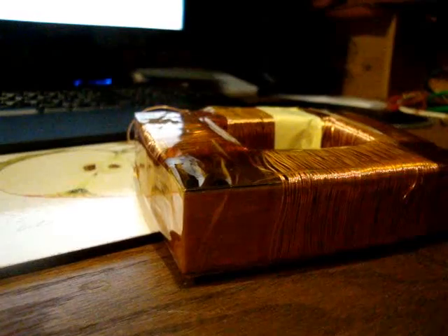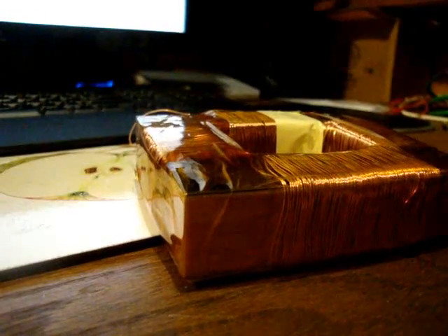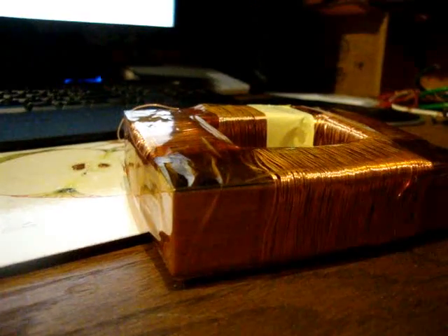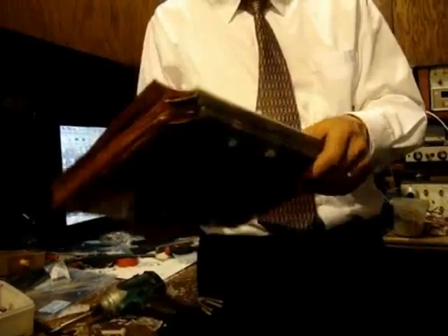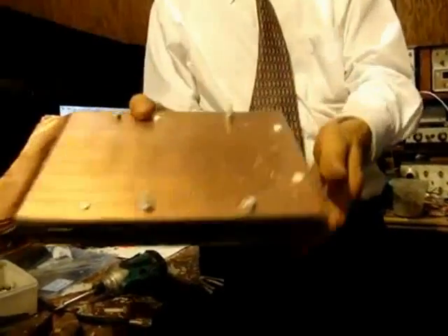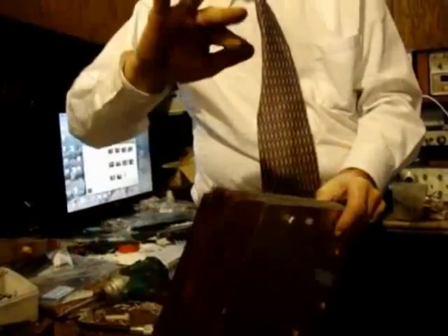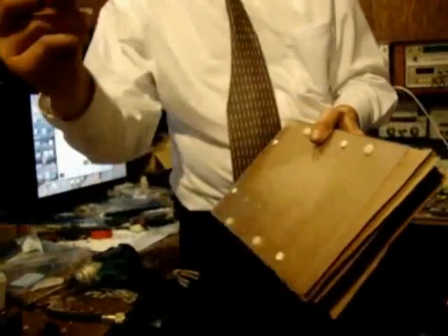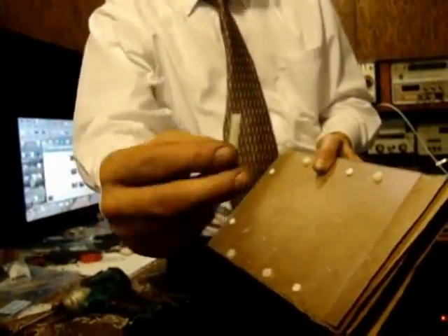Yeah, it's interesting. There's a lot of surface area around this core because each side of the core is about 5 inches in length. So I have 4 sides of 5-inch length, and the number of turns per side: one side has basically 50 turns of secondary, the other side has 70 turns of secondary, 50 and 70. So that's the 4 sides. And between primary and secondary, the flat foil is underneath at the bottom, and then the other gauge wire is right on top of it, separated by Kapton tape. So the Kapton tape is basically a triple insulated system.